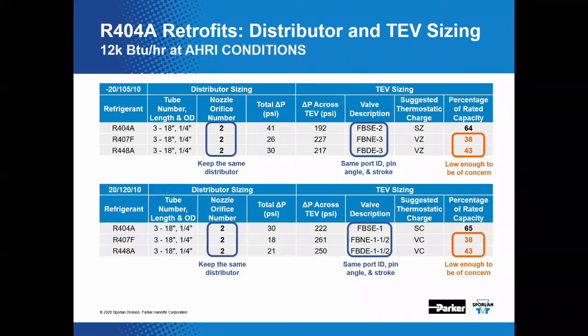Actually, they are. In this case, the internal diameter, the pin angle, and stroke of nominal 3-ton valves for 407F and 448A are the same as for a nominal 2-ton 404A valve. Pretty interesting there. That gives us 38 and 43% loading on these products. Not necessarily a showstopper, but low enough to be of concern. Performing the same exercise for a medium temp system, we get the same relative results. We need to take a closer look at those existing R404A valves, especially considering they will have a low temp Z charge or a medium temp C charge instead of the R22 designated VC and VZ charges that would be recommended.